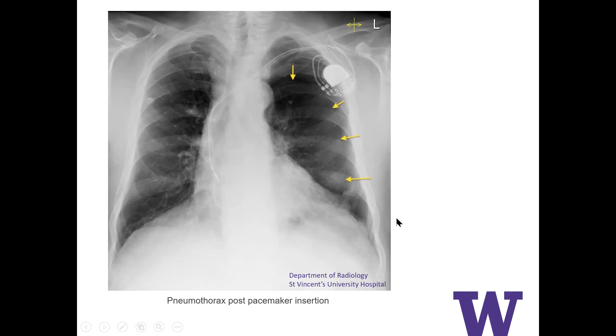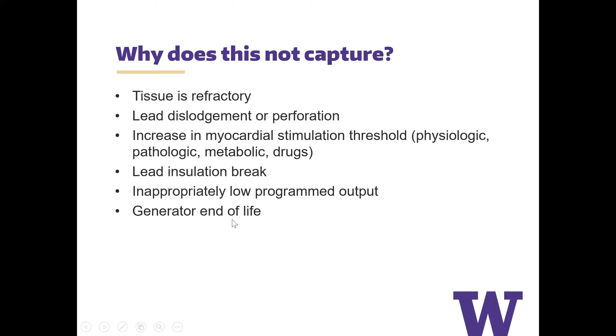So how do you troubleshoot? Why does the pacemaker not capture? It could be that the tissue is in refractory phase. It could be because the lead got dislodged or perforated through the myocardium. It could be that there's an increase in myocardial stimulation threshold, which could be physiologic, pathologic, metabolic, drug-related, a number of different things. It could be lead insulation break. It could be programmed too low of an output. If the stimulation threshold had risen, because of whatever other factors, and you're not programmed to a high enough output, you're not going to capture. Or it could be that the battery is dead, generator is at end of life.